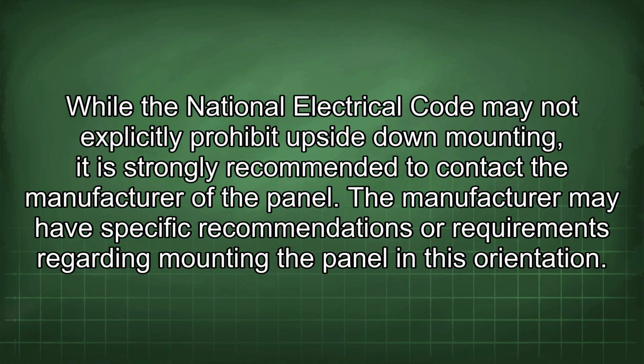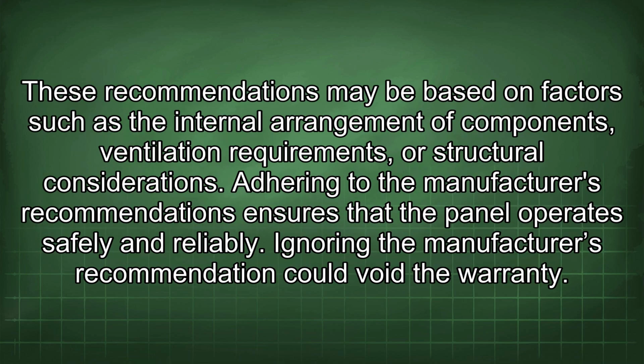While the National Electrical Code may not explicitly prohibit upside-down mounting, it is strongly recommended to contact the manufacturer of the panel. The manufacturer may have specific recommendations or requirements regarding mounting the panel in this orientation. These recommendations may be based on factors such as the internal arrangement of components, ventilation requirements, or structural considerations. Adhering to the manufacturer's recommendations ensures that the panel operates safely and reliably. Ignoring the manufacturer's recommendation could void the warranty.